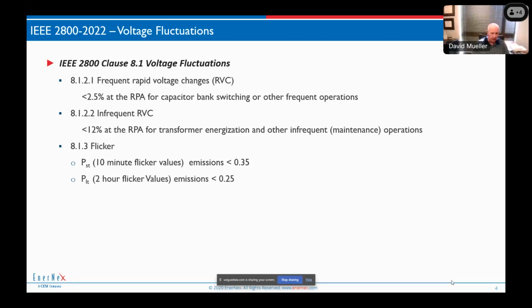As you switch in a cap bank, you're going to raise the voltage. Infrequent rapid voltage change: transformer energization is far and away the most important category here. This 12% requirement, I found out, actually came from the National Grid in the UK, but it was adopted by IEEE 1453, which is the flicker standard, and it is mentioned in 2800.